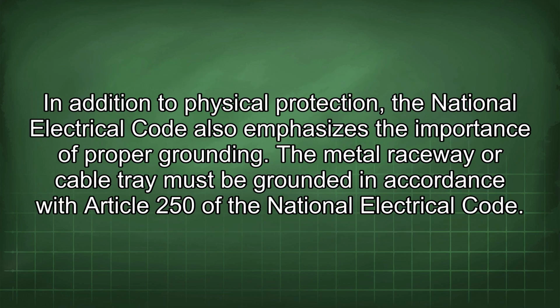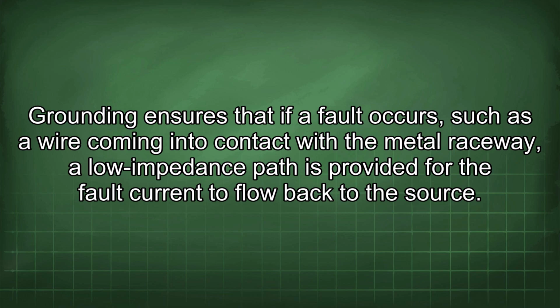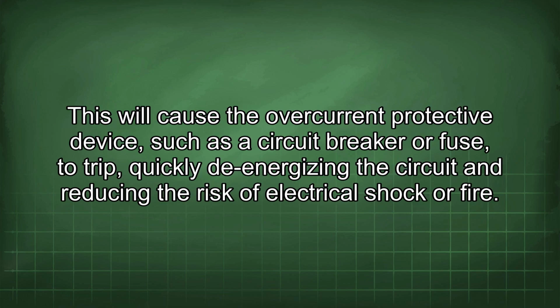In addition to physical protection, the National Electrical Code also emphasizes the importance of proper grounding. The metal raceway or cable tray must be grounded in accordance with Article 250 of the National Electrical Code. Grounding ensures that if a fault occurs, such as a wire coming into contact with the metal raceway, a low impedance path is provided for the fault current to flow back to the source. This will cause the overcurrent protective device, such as a circuit breaker or fuse, to trip, quickly de-energizing the circuit and reducing the risk of electrical shock or fire.